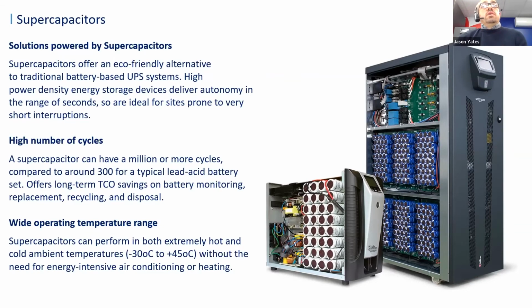to deliver autonomy in a range of seconds. Now, when I say a range of seconds, they can operate anywhere from 5 seconds up to a couple of minutes. So they're ideal for sites prone to very short interruptions or where they have rapid online generation. They obviously can offer a high number of cycles. A supercapacitor can have 1 million or more cycles compared to around 300 of a typical lead-acid battery. They offer long-term total cost of ownership savings over battery monitoring, replacement, recycling, and disposal.